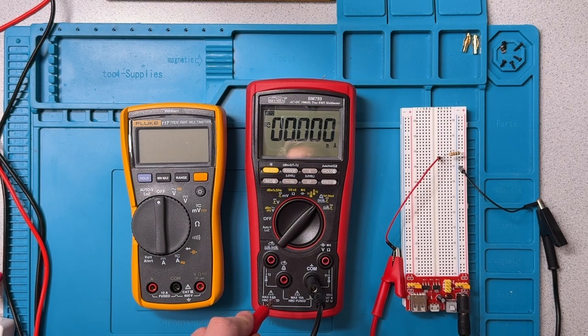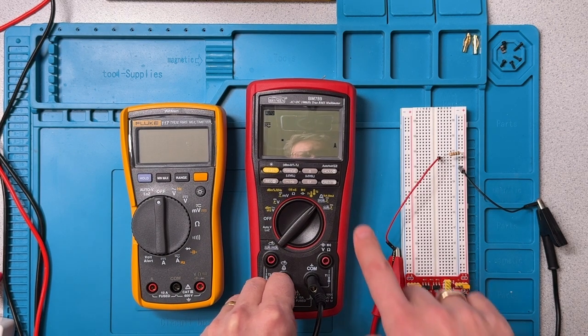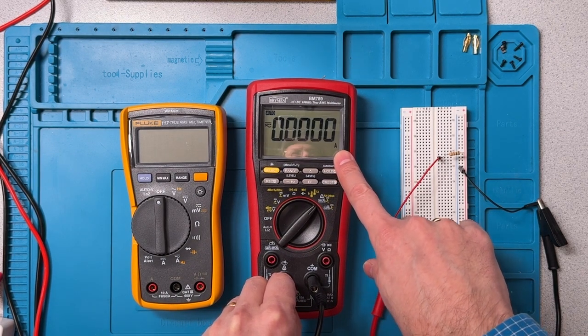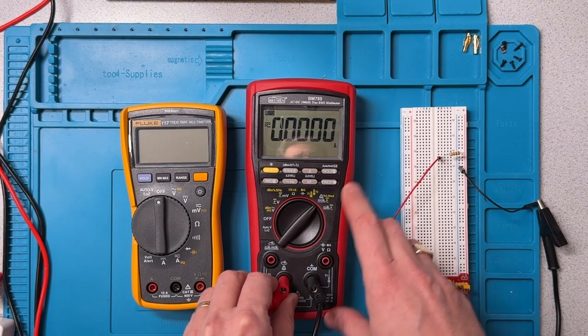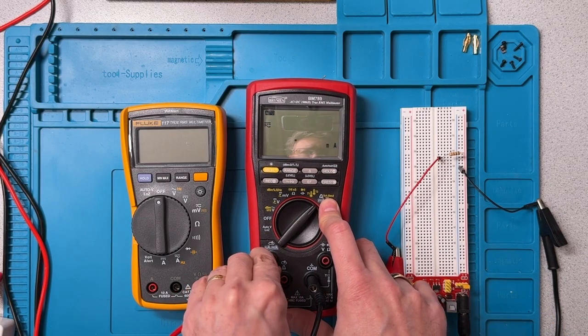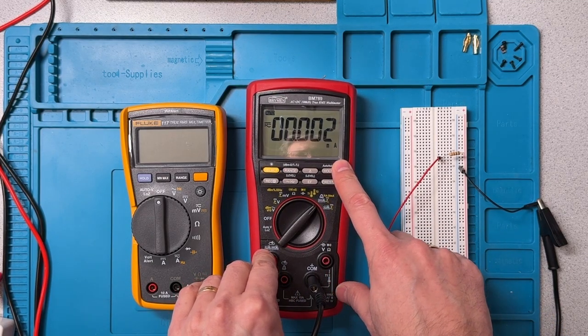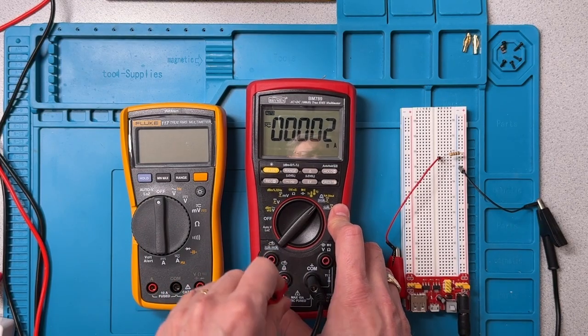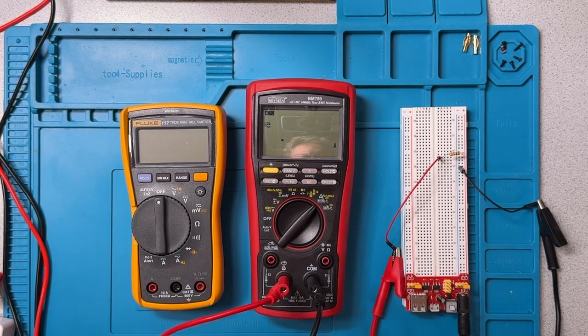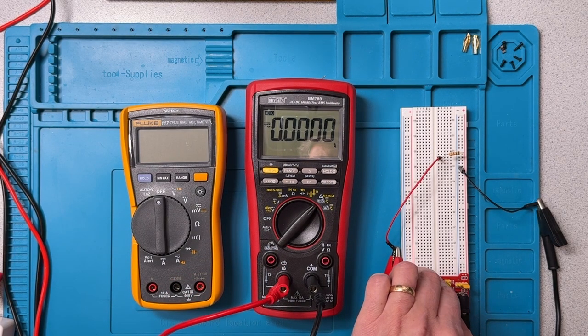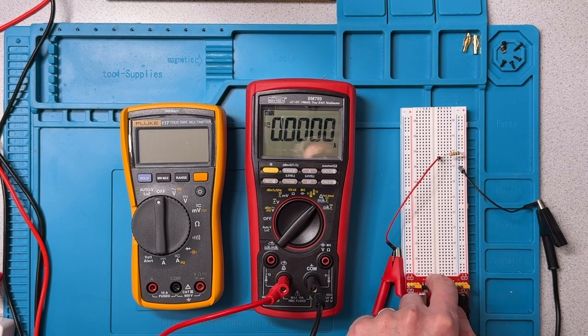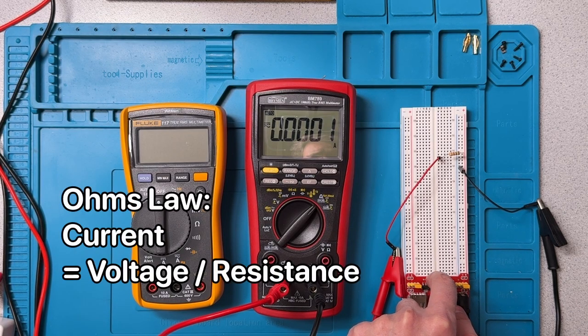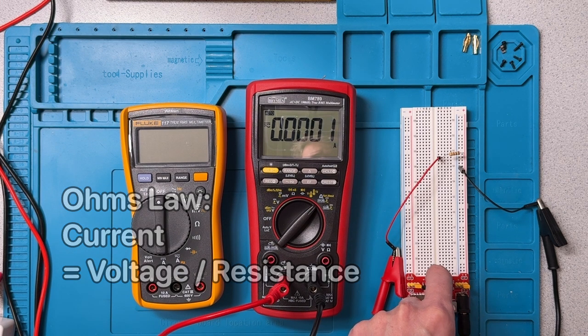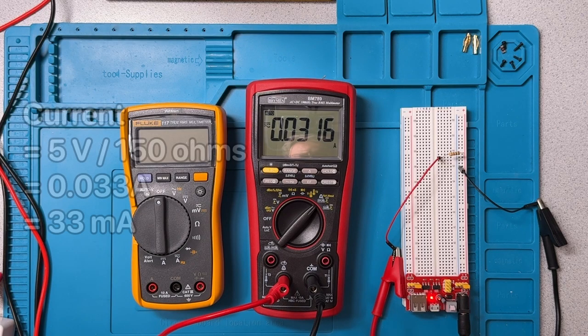One of the things to notice is when I plug the probe into the amp range, the Brymen here can detect that it's the amp range. If I plug it here into the milliamp range, it detects that it's the milliamp range. So we're going to start out in the amp range, and now I'm going to turn on the circuit. If we were to do this calculation with Ohm's law, we would come out with about 32 or 33 milliamps. Let's look at what we get when we have the circuit on here.